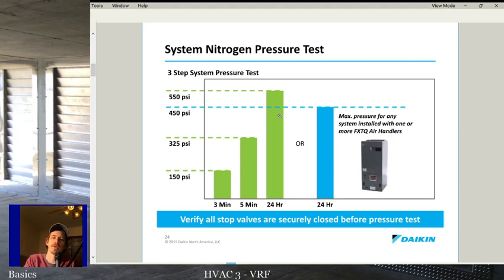You want to do the longest pressure test that time will allow. And I know most systems you're not going to be able to do a 24-hour pressure test, but if you're able to do a 24-hour pressure test, then do it. All right? If you're not able to do a 24-hour pressure test, do the longest pressure test you can. And your pressure test should start at about 50 to 150 psi. Let those sit for a couple minutes. Make sure you have no leaks. Take that system up to 300-ish psi. Let that sit for a few more minutes.